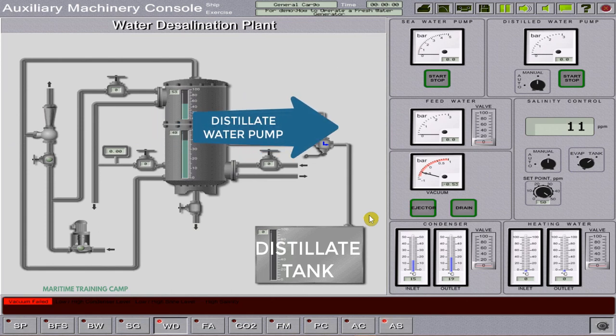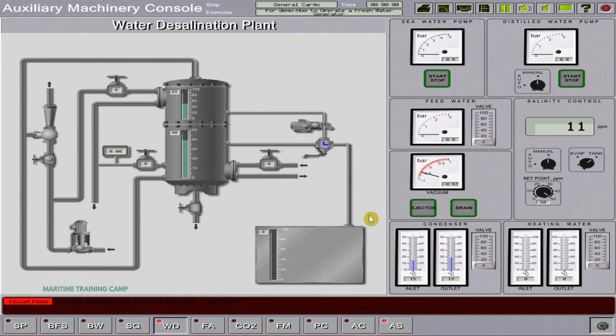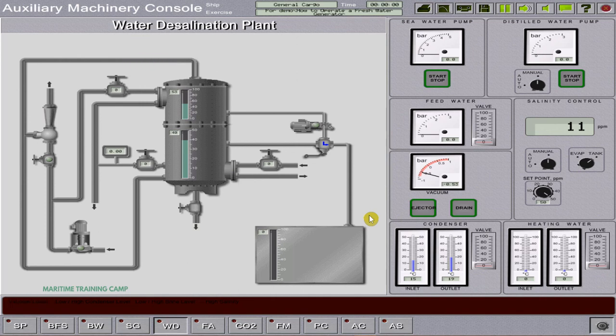The condensed vapor is pumped out into the distillate tank, with a capacity of 0.5 to 10 cubic meters per day. The water level in the evaporator is maintained at a constant level by the overflow. Part of the feed water turns to distilled water, whilst the remaining brine is constantly pumped out of the evaporator by the ejector. As a rule, the plant operates in automatic mode.